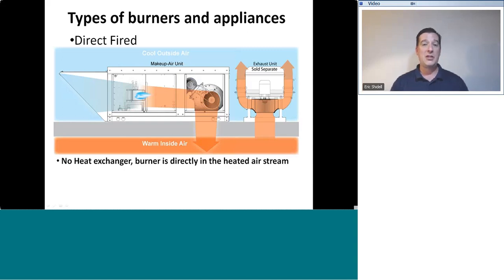That air is being brought in such a significant volume that complete combustion is almost completely assured. There should never be a problem with not enough combustion air. In fact, if you remember our flame temperatures, on natural gas being in that 1800 to 2000 degree range, and realize that makeup air units are generally going to be providing a supply air temperature of about 70 degree air, you realize that there is all kinds of outside air being brought in to provide both the combustion air supply and the airstream for the makeup air. Some jurisdictions do not allow direct-fired burners because they are concerned about combustion products building up in the atmosphere, but they are very, very common wherever they are allowed because they're economical, they're very effective, and in general, they're incredibly safe as well. So this would be what we would call a direct-fired makeup air unit.